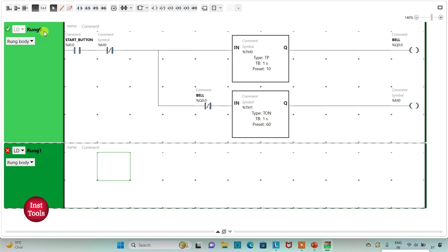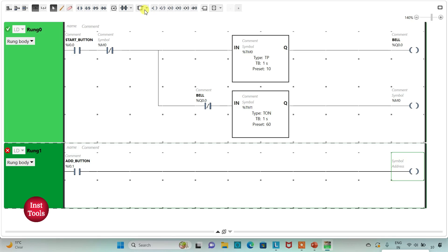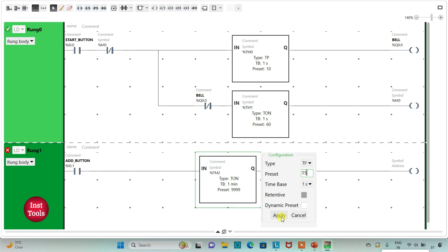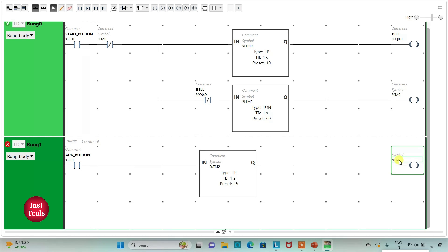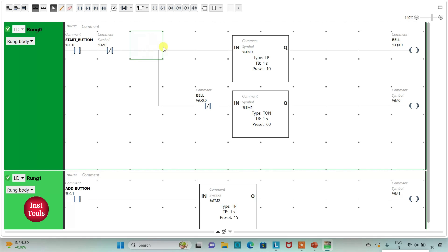I will add a new rung and insert a normally open contact, assigning address I0.1 with the symbol 'add button'. Then I will insert a coil and a timer — that will be a TP timer. I will change the time base to 1 second and the preset value to 15, then click Apply. I will assign address M1 to this coil.